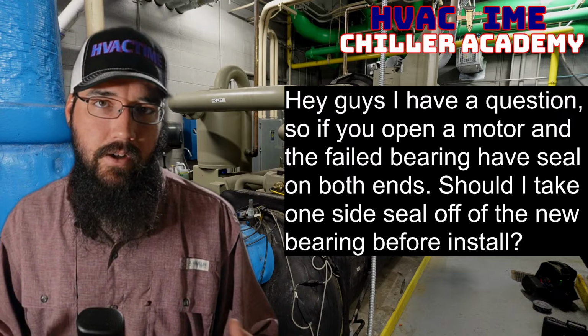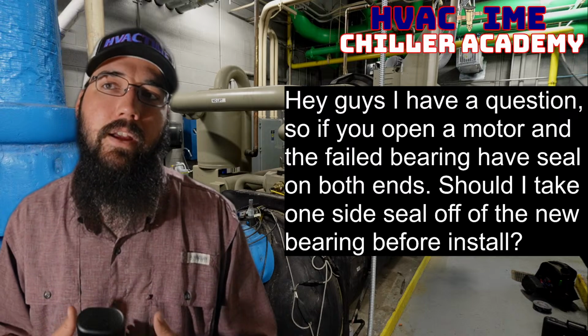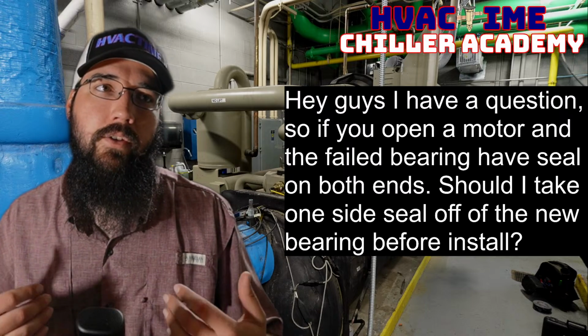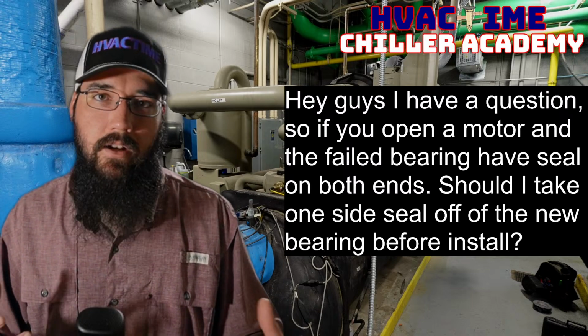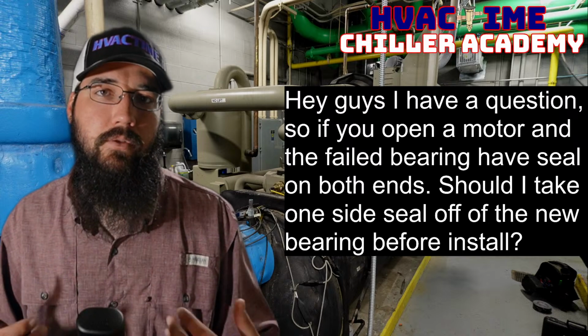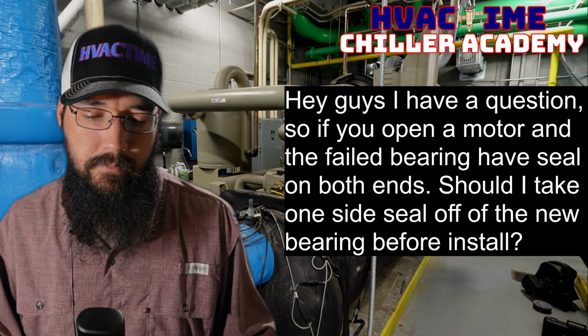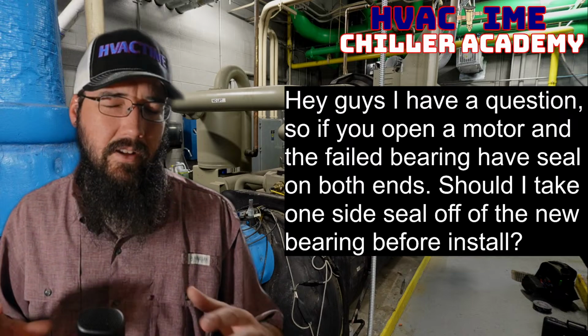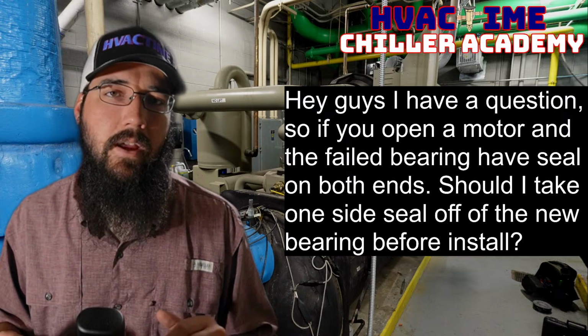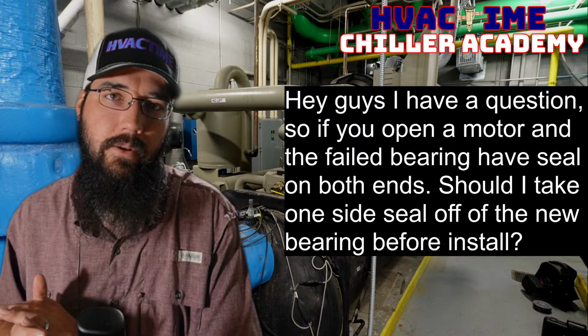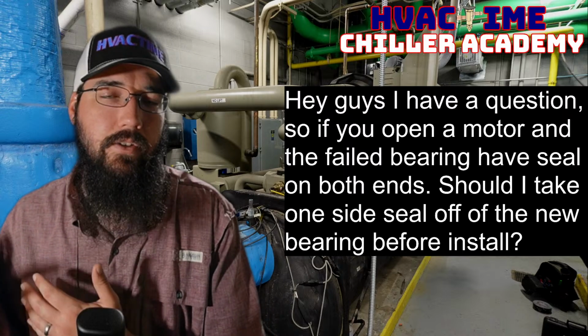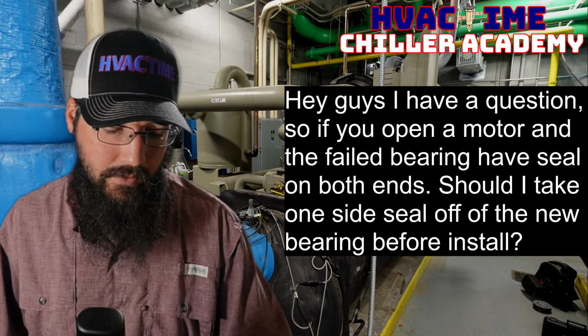Those sealed bearings, while they're great in theory, depending on what they're being connected to, if you've got a lot of heavy loads on that bearing, tend to wear out fast. I'm not saying they can't handle it, but they wear out faster than I would consider a properly greased standard bearing would in that same environment.